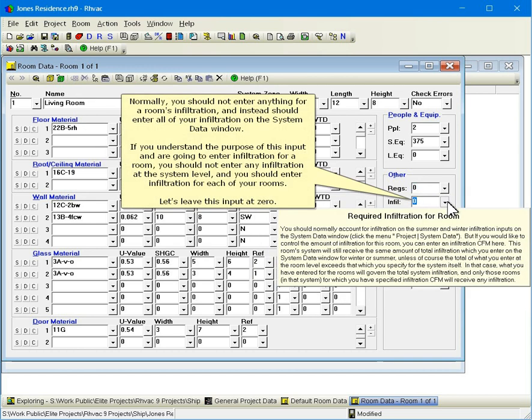Normally, you should not enter anything for a room's infiltration, and instead should enter all of your infiltration on the system data window. If you understand the purpose of this input and are going to enter infiltration for a room, you should not enter any infiltration at the system level, and you should enter infiltration for each of your rooms. Let's leave this input at zero.